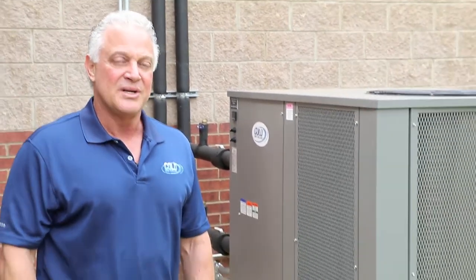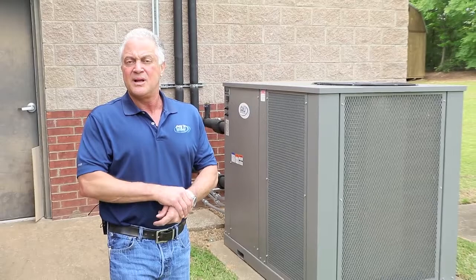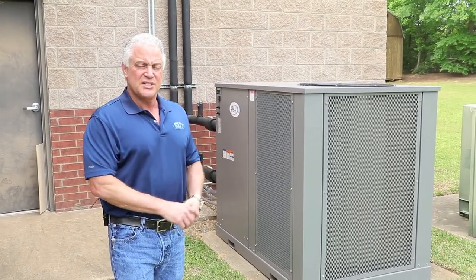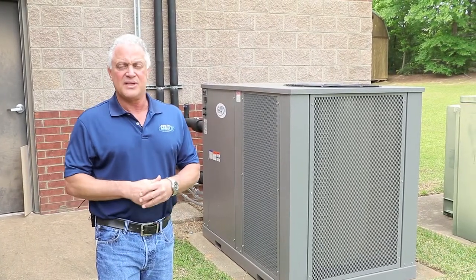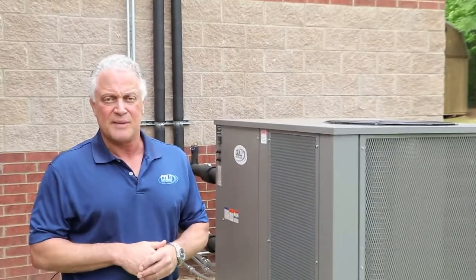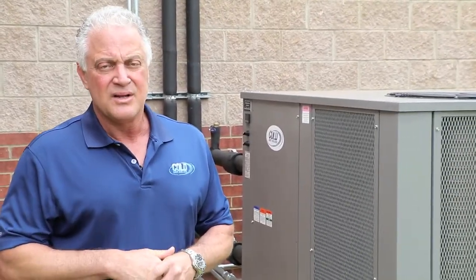Hi, my name's Mike Marone from Cold Shot Chillers, and we're here this afternoon to commission a brand new air-cooled water chiller, model ACWC90QDM. It's a 7.5-ton machine supporting a Varian TrueBeam linear accelerator. This machine is designed to handle a wide variation of heat loads quite often found in this application, and still providing the long, reliable service that's needed for long-term service.